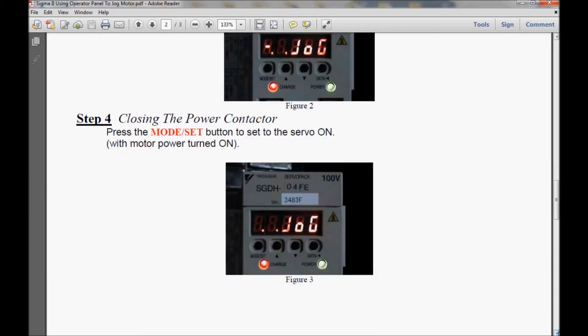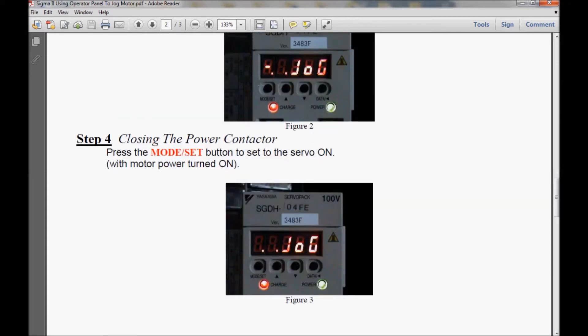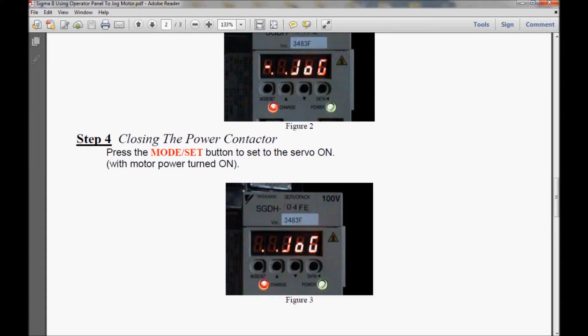In step 4 I will be closing the power contactor in the drive. If you look at the picture that I have here, there is a dash in figure number 2 in the last section of the display. And in step 4, in figure 3, there is no dash. So that means that with the dash, the drive is still in base block, although the display reads jog. So when you close that contactor, it applies power to the motor and you are no longer in base block.